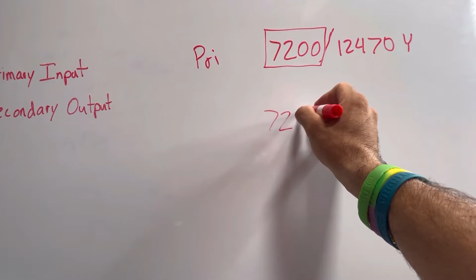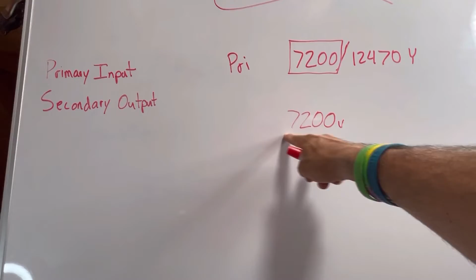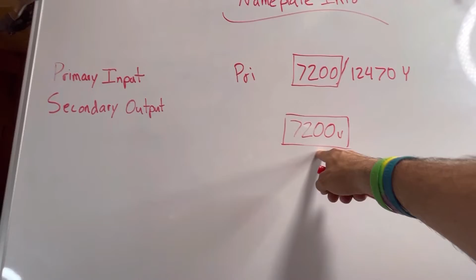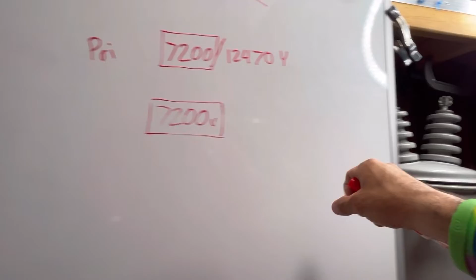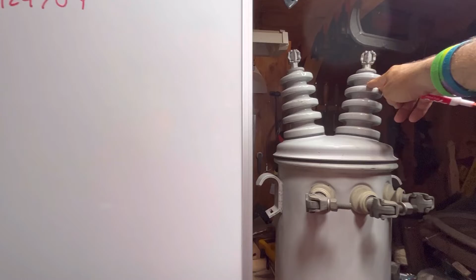So another way that nameplates will tell you what the primary input needs to be, sometimes they'll just give you one straight up number. Sometimes they'll just say 7200 volts. So if it just says 7200 volts, that's just what it is. It just needs that voltage. And this one, this type of nameplate, will also go on a transformer that has two insulated primary bushings. So this transformer, you can give it 7200 volts, whether that be either a phase-to-phase connection, they're both insulated, so we're good to go there, or a phase-to-neutral connection, right? So we can throw a phase in one of them and a neutral in the other. And finally, the last one that you're really going to see in terms of single-phase transformers in the field is you're going to see this one.